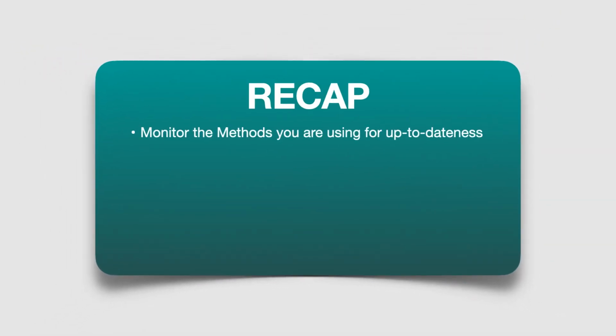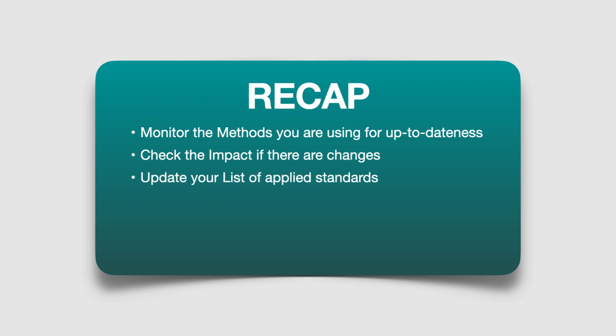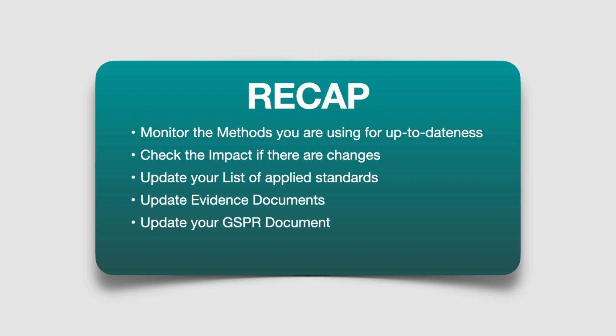Let's recap what needs to be done. We need to look for updates on standards and guidance documents. The possible impact must be checked. The list of applied standards must be updated. Verification documents must be created or updated. Finally, all GSPR documents must be updated.